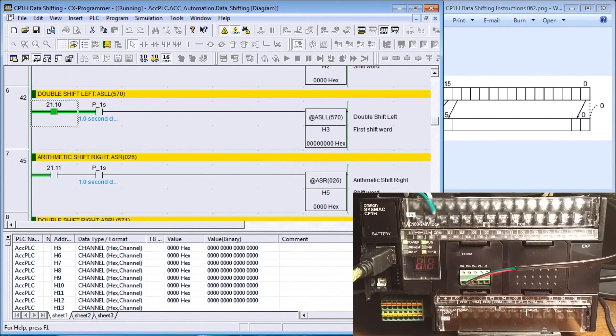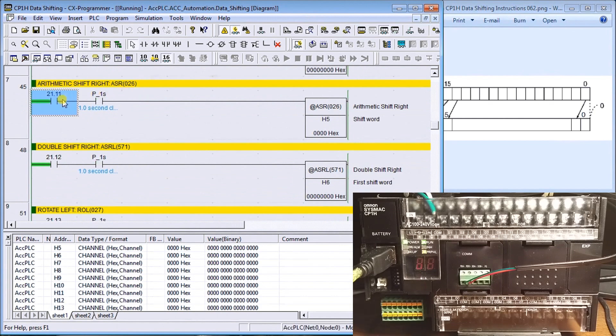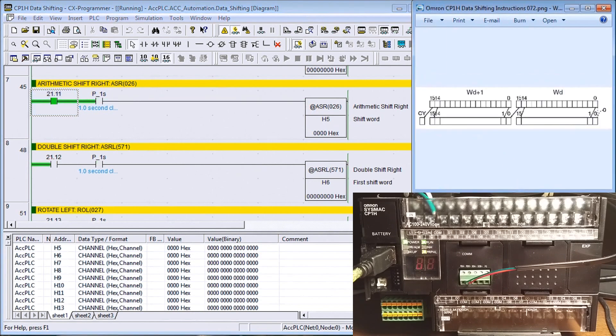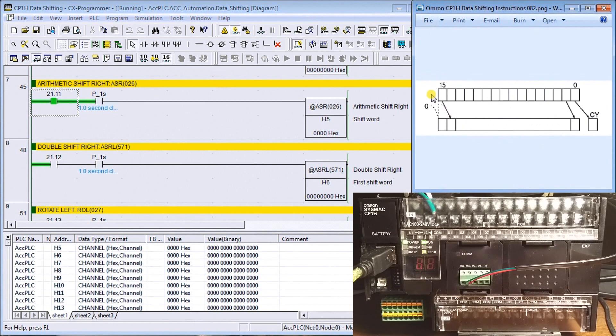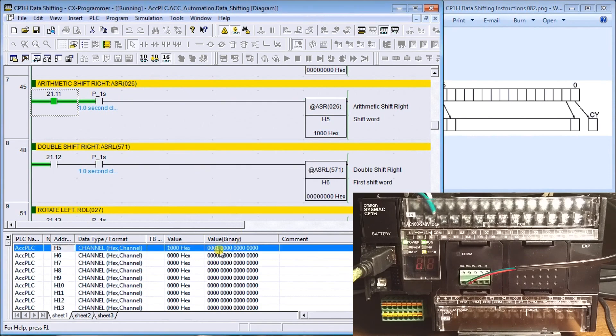The next instruction is the arithmetic shift right. We're using the differentiate-up (@ sign) on arithmetic shift right. The shift right puts values into bit 15 and shifts toward the right side, which is equivalent to dividing by two each time. It operates on H5, so we'll put the value 8000 hex in there and watch as that bit shifts right — we're dividing by two with each pulse.